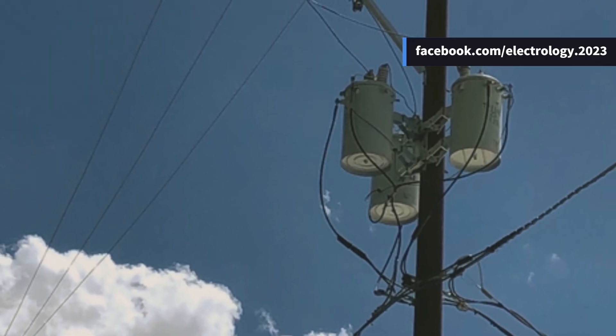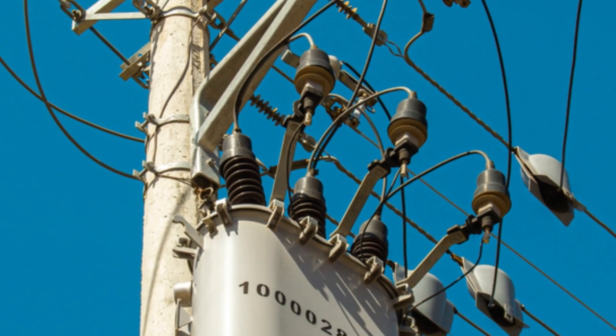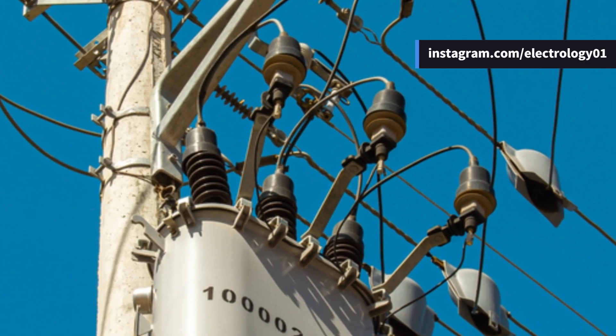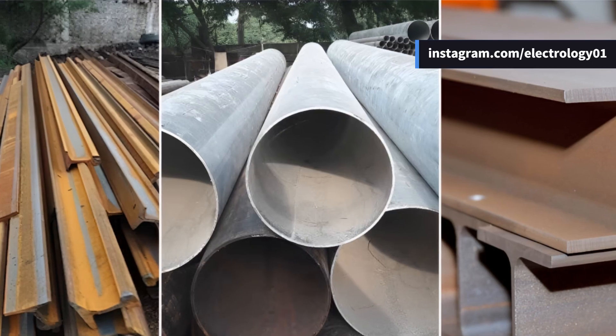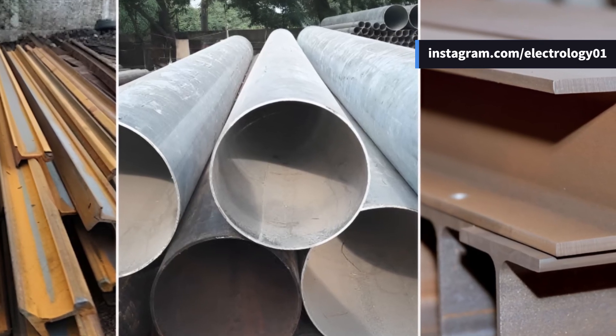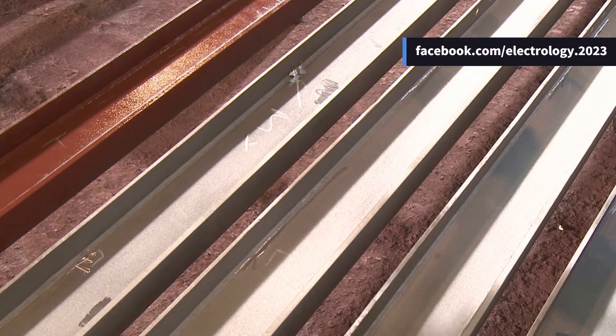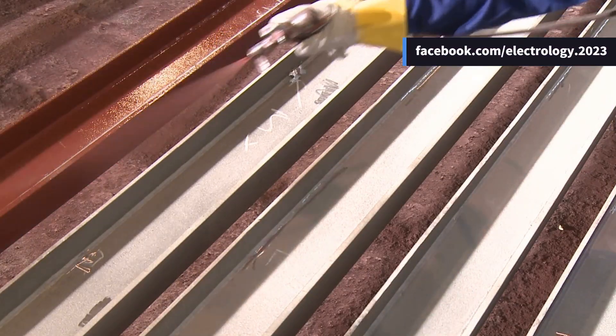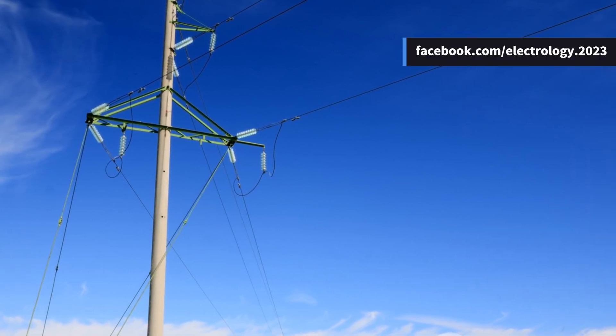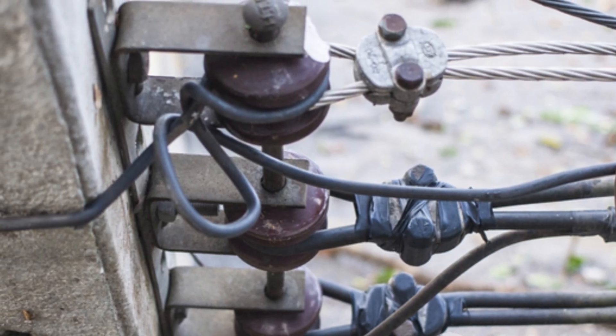Moving on to the urban champs — steel poles. These are stronger, last longer, and allow longer spans. You'll mostly find them in cities replacing wooden types. They come in three styles: rail poles, tubular poles, and rolled steel joists. They must be painted or galvanized to protect from rust and increase lifespan — think of them as the stylish but tough cousins of wooden poles.